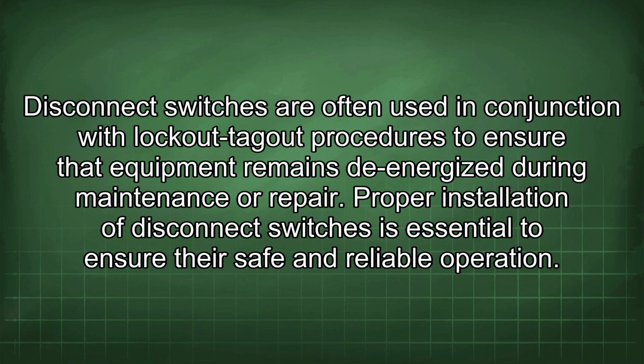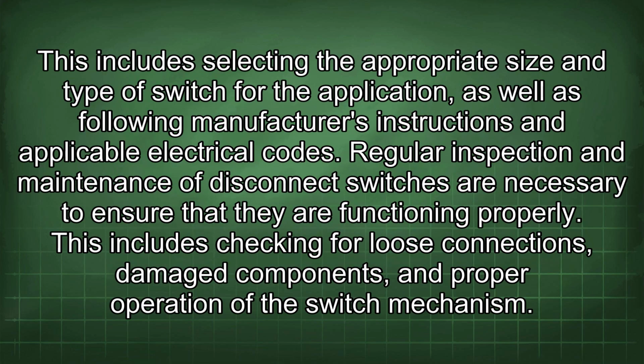Disconnect switches are often used in conjunction with lockout-tagout procedures to ensure that the equipment remains de-energized during maintenance or repair. Proper installation of disconnect switches is essential to ensure their safe and reliable operation. This includes selecting the appropriate size and type of switch for the application, as well as following manufacturer's instructions and applicable electrical codes. Regular inspection and maintenance of disconnect switches are necessary to ensure that they are functioning properly.